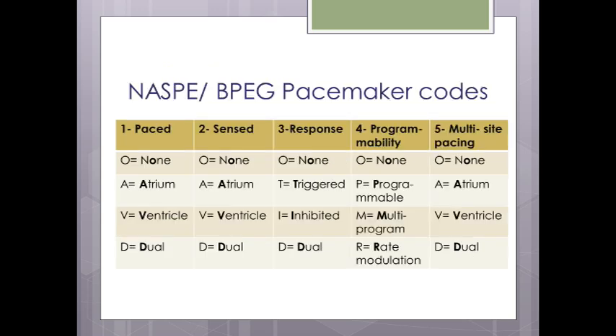Pacemaker codes consist of five international positions or letters that code pacemaker function and characteristics. The first position is the chamber paced, which may be None, Atrium, Ventricle, or Dual. The second position is the chamber sensed, also None, Atrium, Ventricle, or Dual.